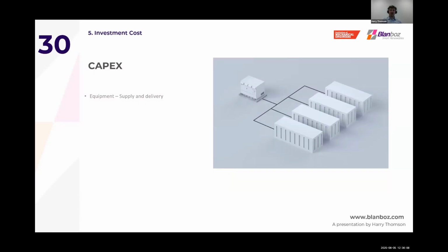Next, we have the CapEx, the actual cost of building the system. This includes the cost of equipment, which predominantly composes of batteries, but also cabling, transformers, and control hardware. From our experience, this can range anywhere from $90 per kilowatt hour to $200 per kilowatt hour, and can take up to 60 to 70% of total CapEx.